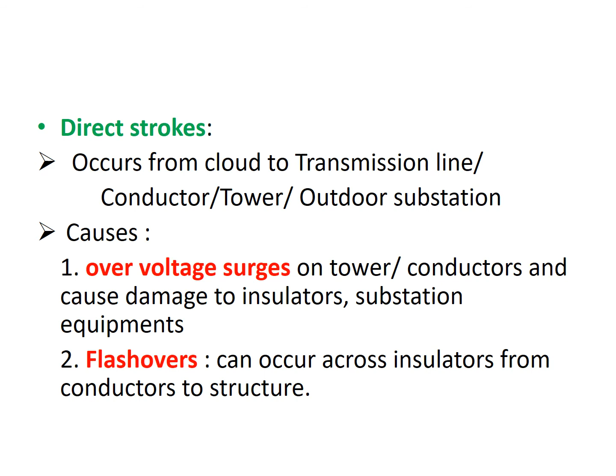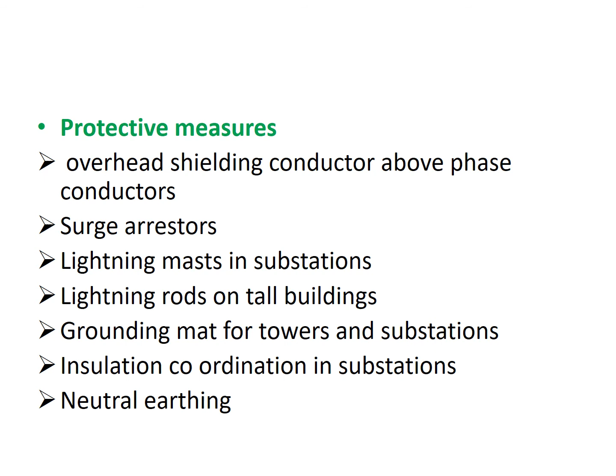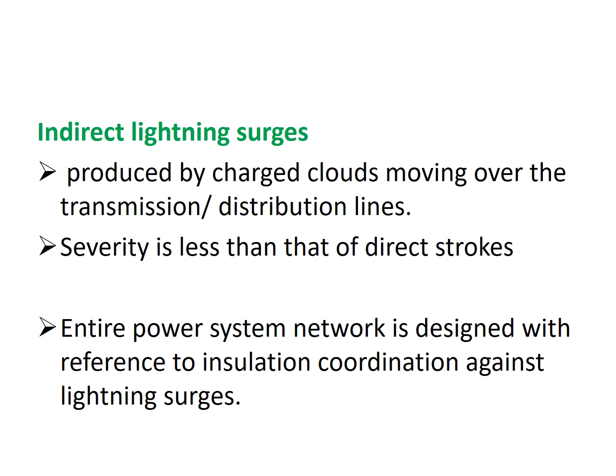The protective measures that can be utilized here are overhead shielding conductors, above-phase conductors, surge arresters, lightning masts in substations, lightning rods on tall buildings, grounding mat, insulation coordination in substations, and neutral grounding. Indirect lightning surges are produced by a charged cloud moving over the transmission line. Severity is less than that of a direct stroke.